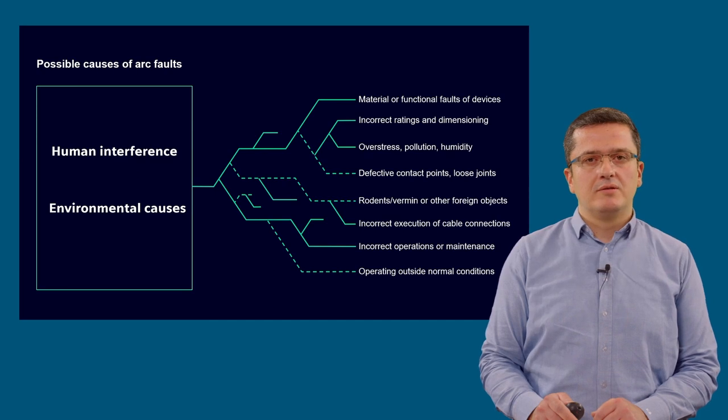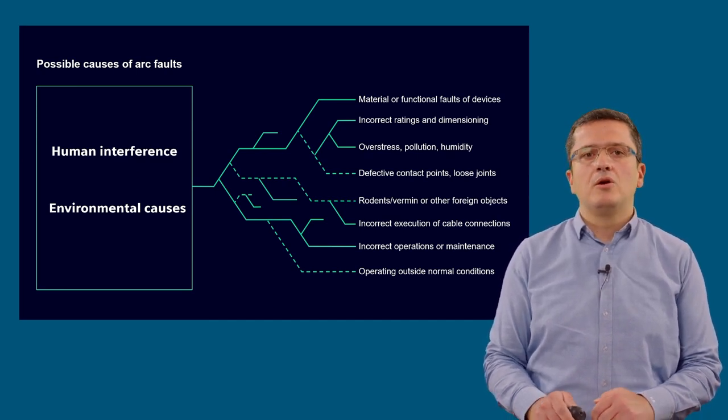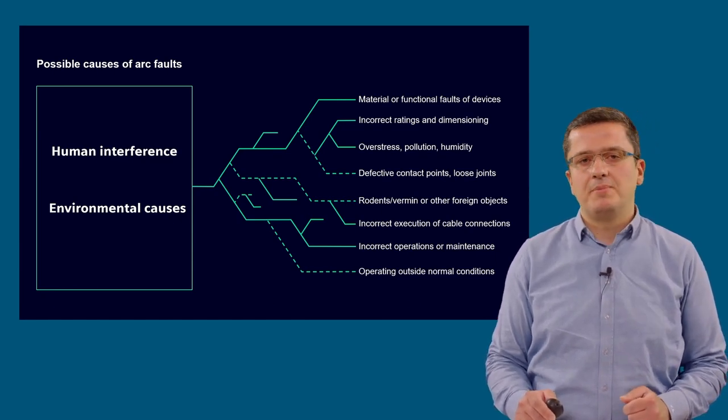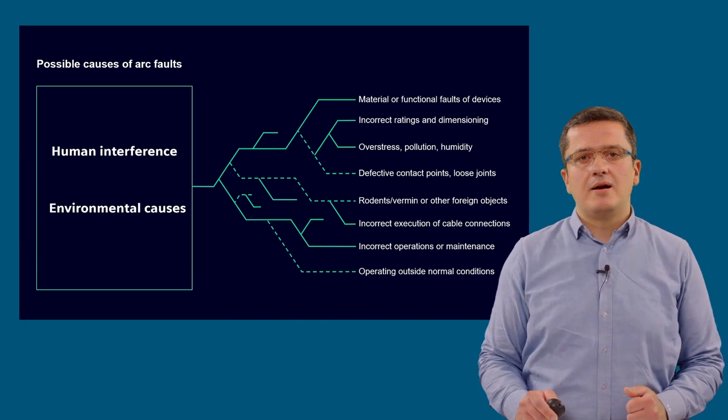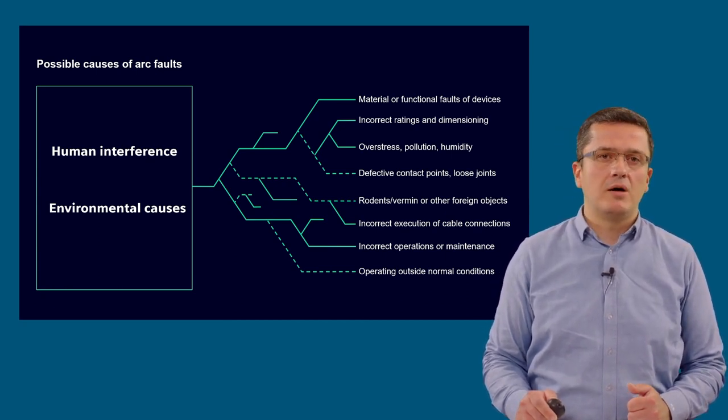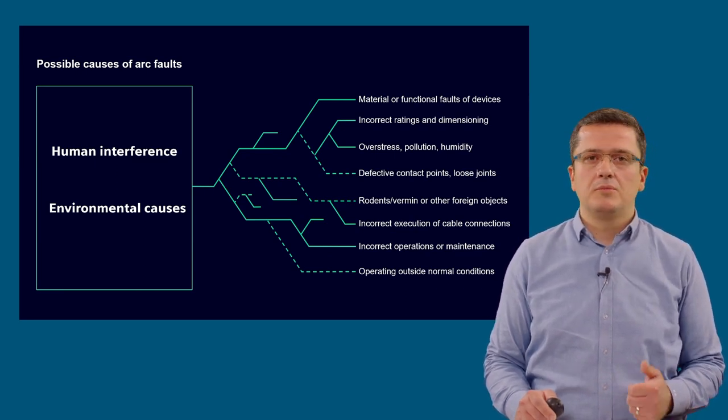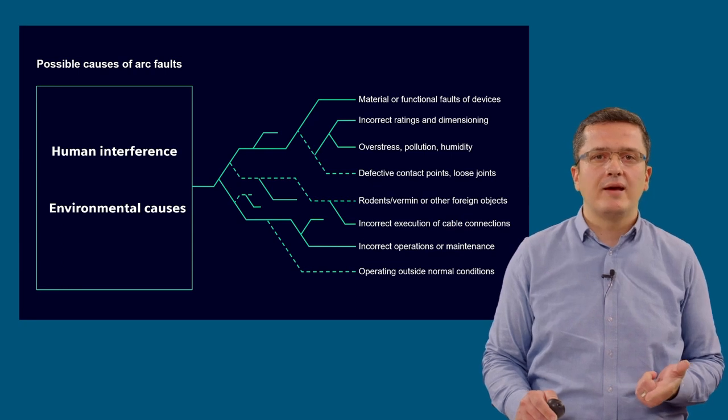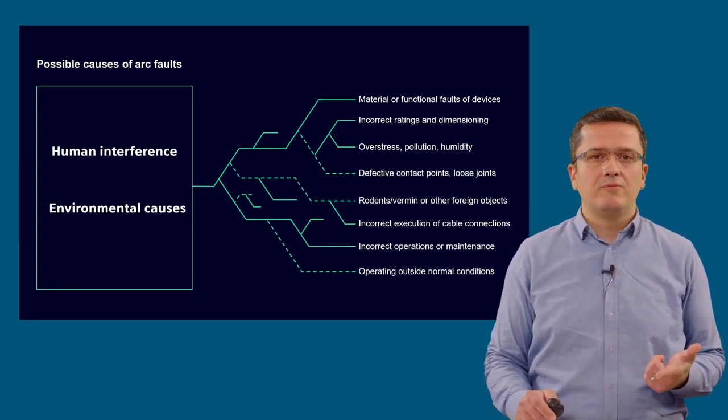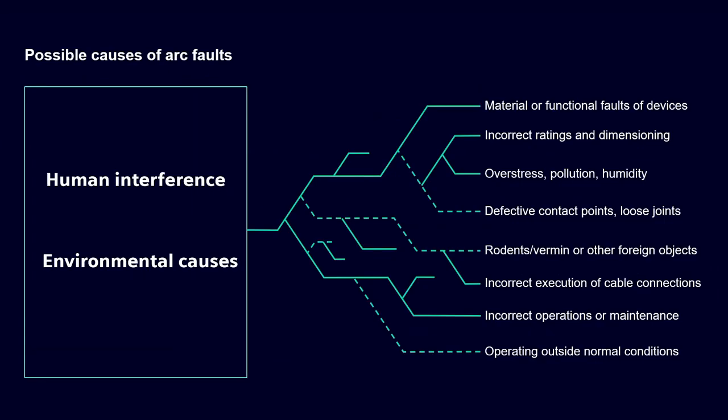The occurrence of an internal arc in a well-designed, type-tested, correctly installed and operated switchgear is improbable, but not impossible. The reasons are mostly linked to human interference or environmental causes. Most repeating causes are loose connections, corrosion causing overheating and further escalating to arcing faults, rodents and vermin entering into the equipment, or deteriorating insulation in time.